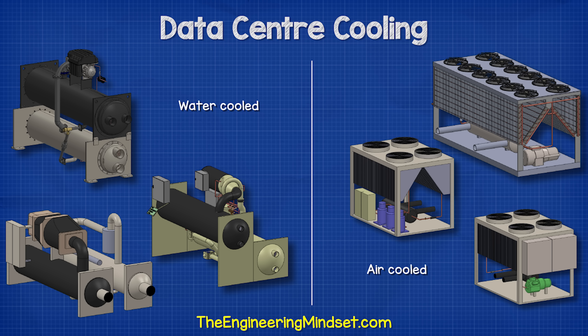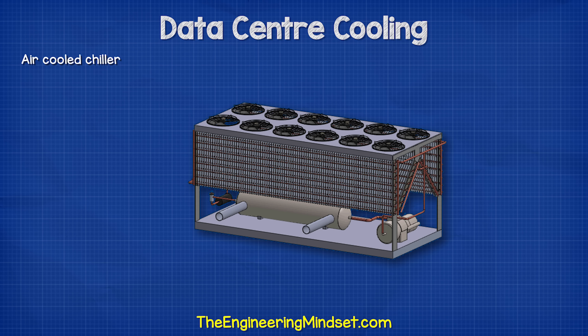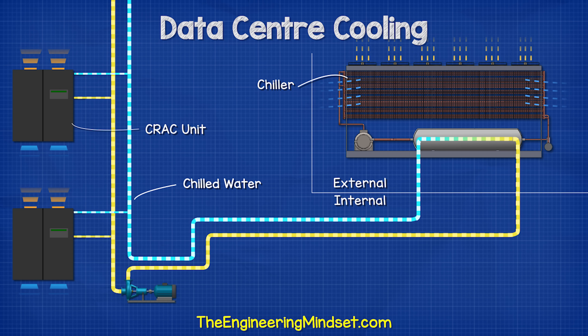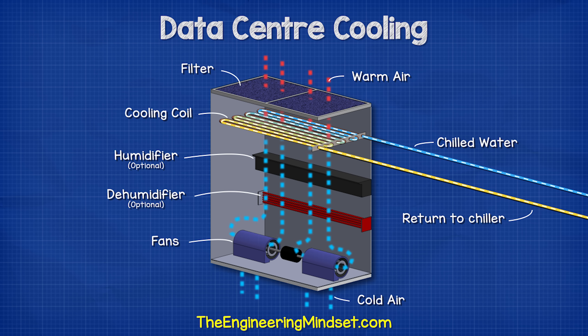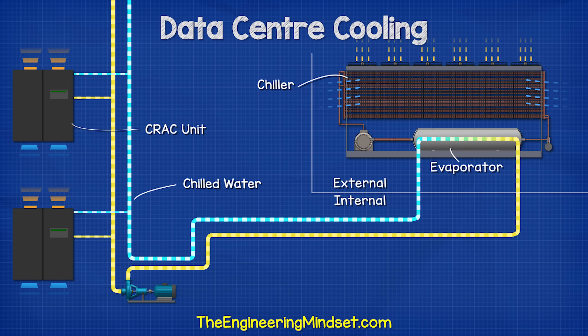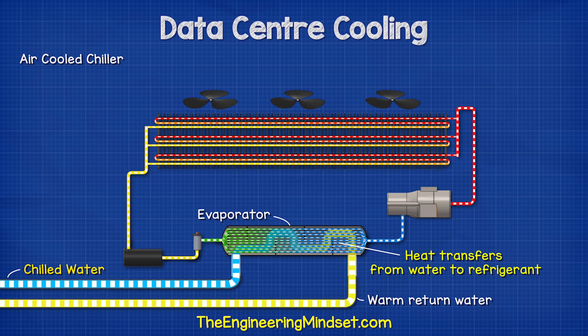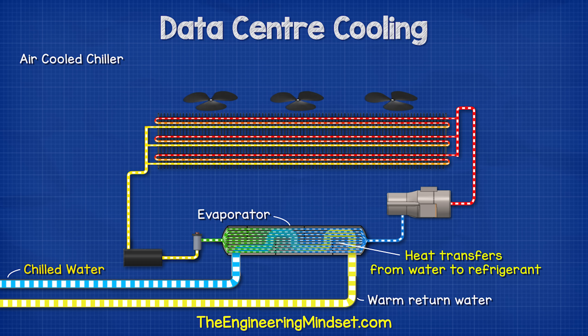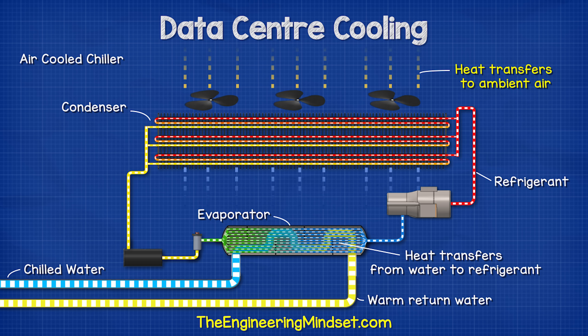Larger data centers will use chillers, either water-cooled or air-cooled type. With air-cooled systems, the chiller is installed externally. This provides chilled water to the CRAC unit, which flows through a heat exchanger to pick up the unwanted heat from the air. The fan moves the hot air over the heat exchanger and once the heat is removed, it is pushed into the void under the floor. The water returns to the chiller where it enters the evaporator and the heat is transferred into a refrigerant. The refrigerant removes the heat from the water and cools it down, then cycles the water around again to collect more heat. The refrigerant flows to the condenser where fans move ambient air over the pipes to reject the heat to the atmosphere, before flowing back to the evaporator to collect more unwanted heat from the water.